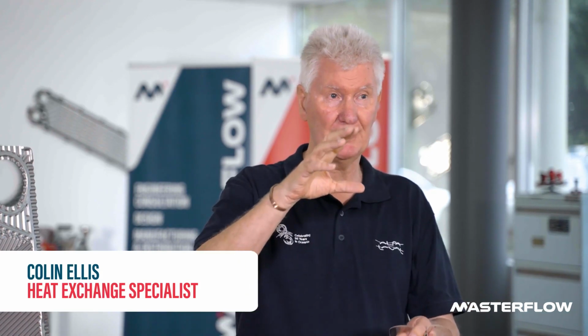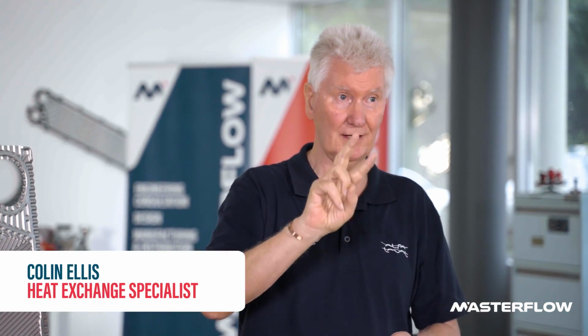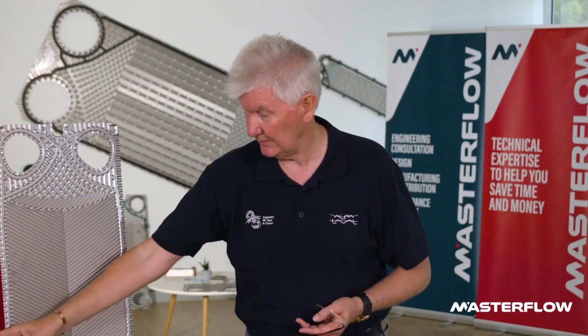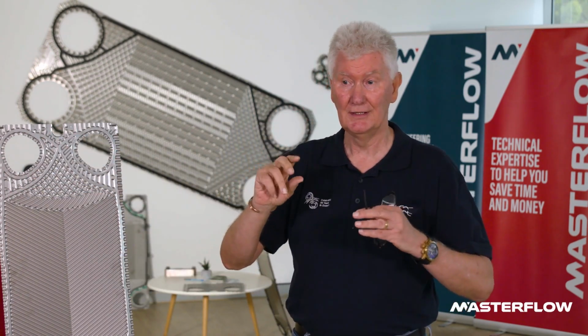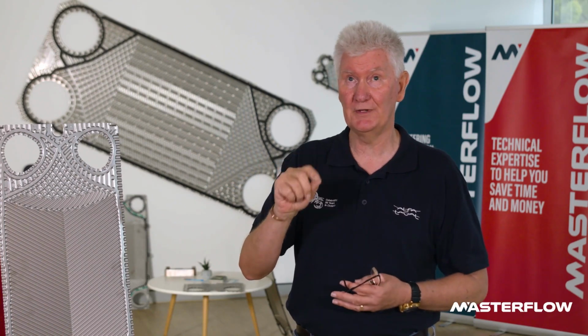Heat transfer area and surface area are one and the same, but in the plate heat exchanger there are actually two different area calculations. There is the heat transfer area used for transferring heat, then there's the total area on the plate. The total area of the plate would be measured top to bottom, side to side. But your heat transfer area is actually inside where the gasket goes. So there are two different areas, and you need to be careful how you specify them in your data sheet.